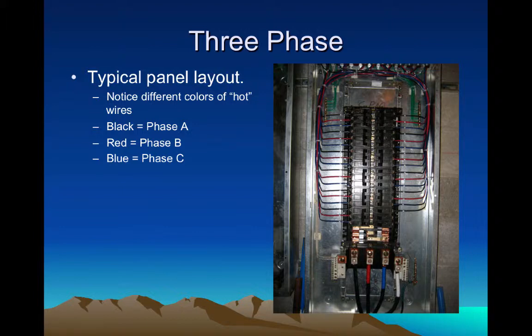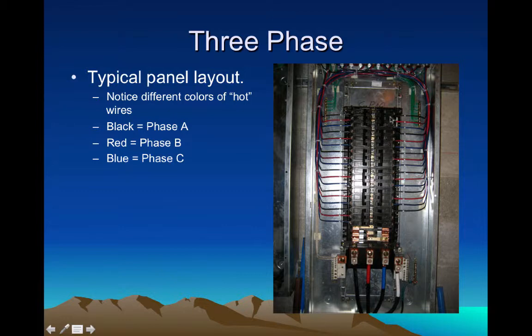When designing your AV systems and powering them, you want to make sure everything is getting power from the same phase. If you need more than one 20 amp or 15 amp circuit and you're in a facility with three-phase power, make sure those circuits are all on the same phase. For example, if the top breakers are labeled Studio A, Studio B, Studio C repeating — you would want Studio A on every third breaker. You would not want Studio A, A, A, then B, B, B, then C, C, C, because then each studio would have three different phases of power feeding those outlets.